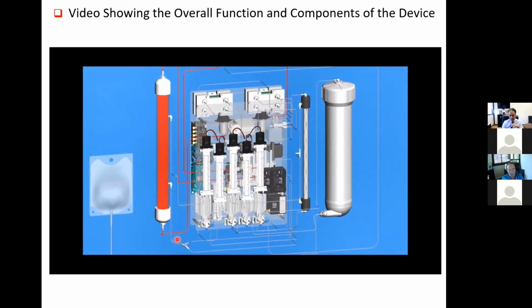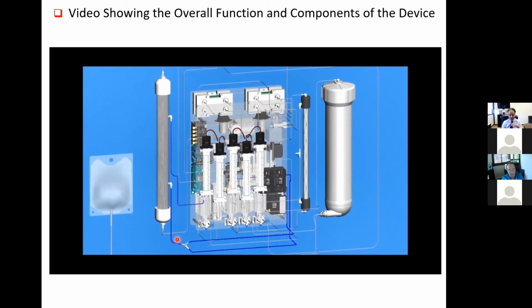The module allows smaller substances dissolved in blood, such as glucose, urea, and ions, to pass through, as shown as the blue stream leaving the bottom of the ultrafiltration unit. From there, the stream flows through a sensor bank to analyze the patient's initial ion and urea levels to determine the removal amount using the smart software. Next, the stream is pumped into an electrodeionization module, which is shown as the blue flow into the top left rectangular module.